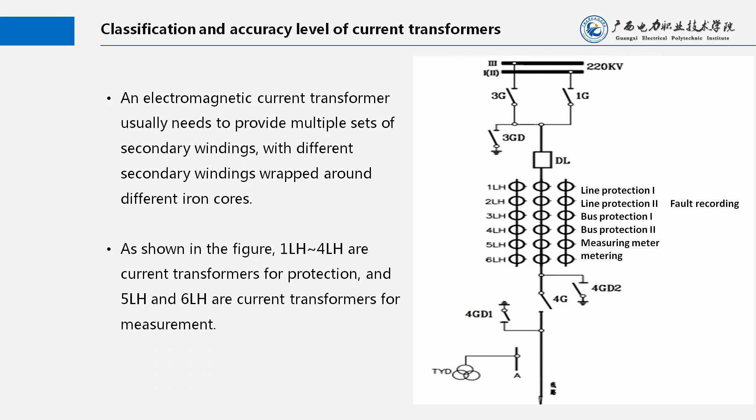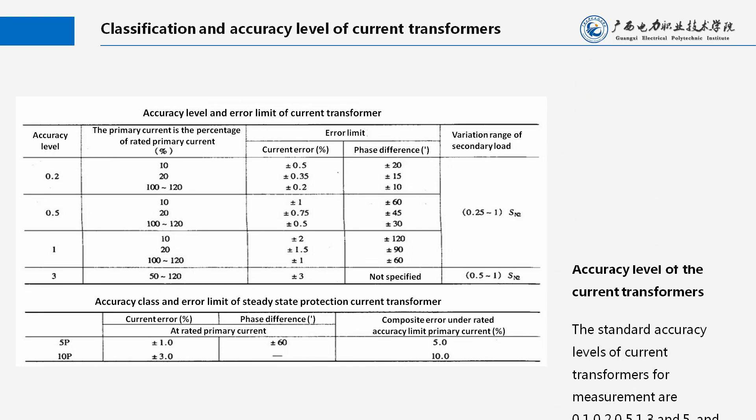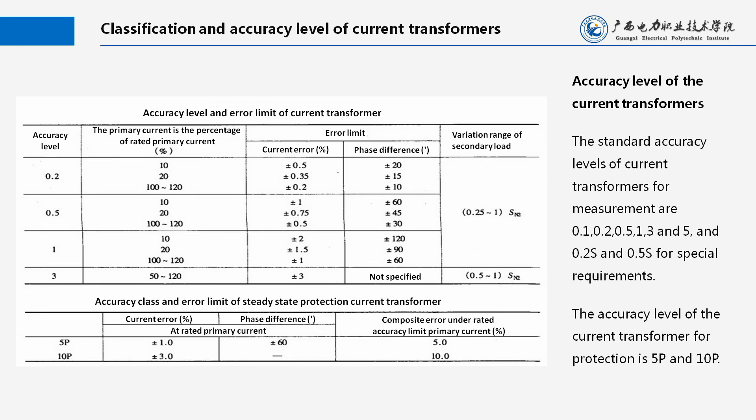As shown in the figure, 1LH to 4LH are current transformers for protection, and 5LH and 6LH are current transformers for measurement. The standard accuracy levels of current transformers for measurement are 0.1, 0.2, 0.5, 1, 3 and 5, and 0.2S and 0.5S for special requirements. The accuracy level of the current transformer for protection is 5P and 10P.